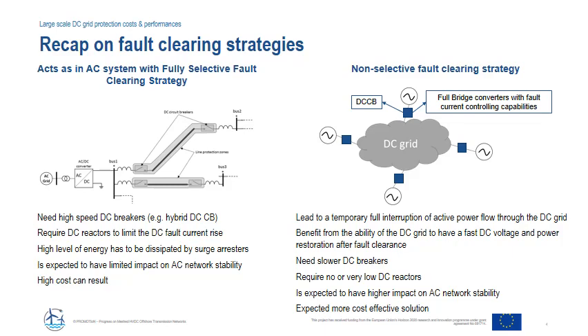The second concept, the non-selective fault clearing strategy, considers the full DC grid as a protection zone. It consists of first isolating the DC grid from any power source in order to suppress the fault current. This isolation can be achieved by installing a DC circuit breaker at each converter output or by using converters with fault current controlling capabilities. Then the identified faulty line is isolated using a high-speed switch or a DC circuit breaker installed at each line end. The power flow is then restored through the DC grid. It leads to the temporary full interruption of active power flow through the DC grid, and as such could have a higher impact on AC network stability. In using slower DC circuit breakers, it is expected to be a more cost-effective protection solution.